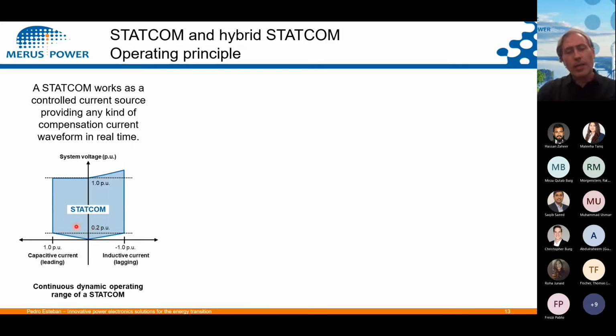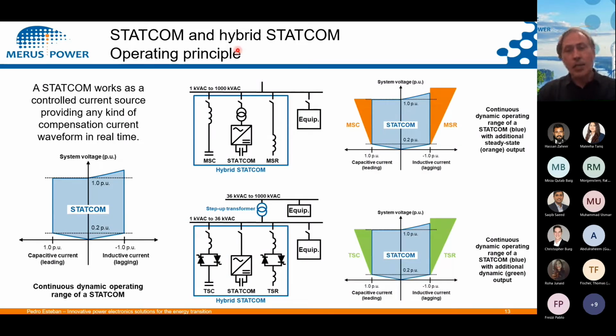The difference with a lot of the conventional or passive solutions, like capacitor banks and reactor banks, is that these devices can still provide a very good output, or even full output, at lower voltages in the system. If we are thinking about a hybrid STATCOM, the only difference is that it will be adding a certain portion that you can see here in the capacitive side or in the inductive side. And there will be a certain speed, depending on whether we use mechanically switched devices or thyristor switched devices. Of course, they will be providing a faster output to customers.